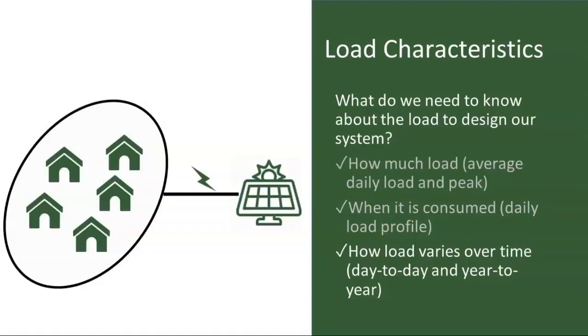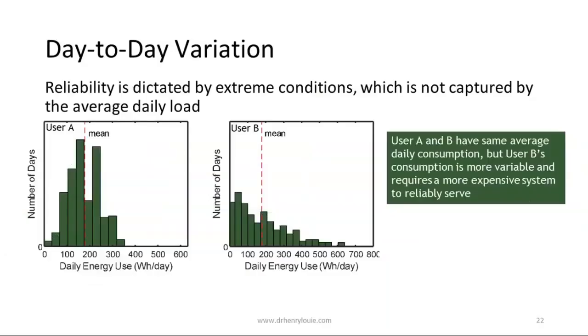We're also interested in how load might vary over time on both short and long time scales. Consider two users with the same average consumption: User A is easier to supply reliably than User B because User A's daily usage is much more consistent. Reliability isn't dictated by the average — it's dictated by extreme events. Perhaps a user has a few days a year where they consume two or three times their average. Those are the days you worry about from a reliability standpoint. We need to understand not only the average but the distribution — the probability that they're going to use two or three times or more than their average — to have a good understanding of the reliability requirements of our system.